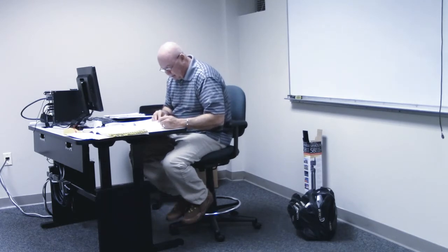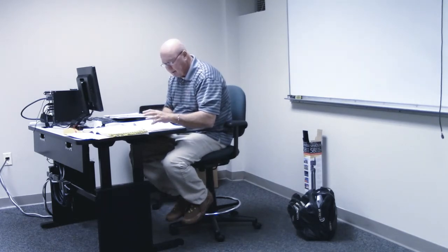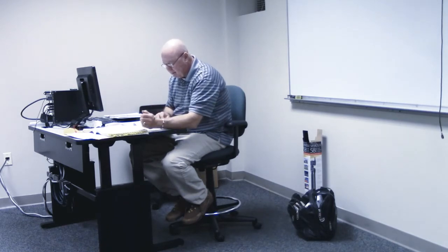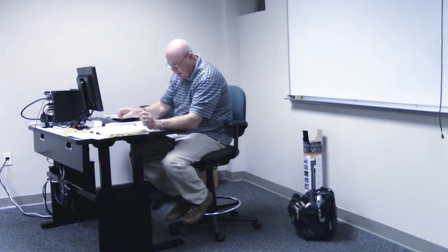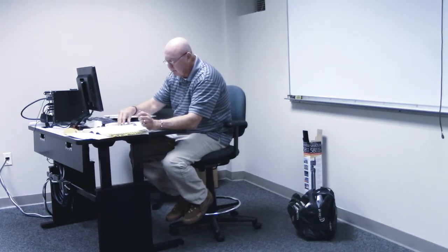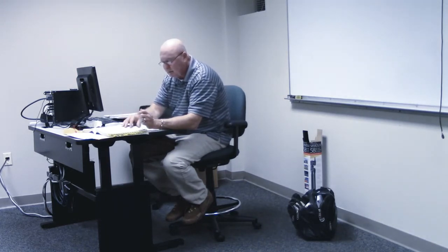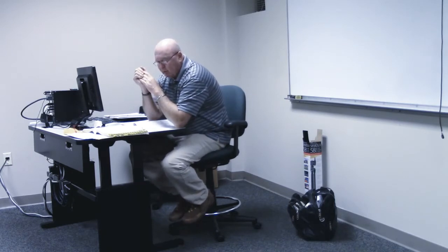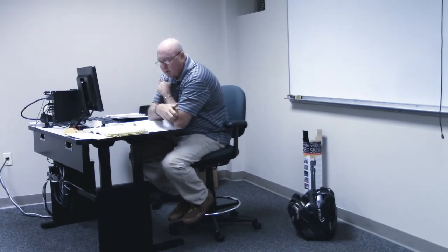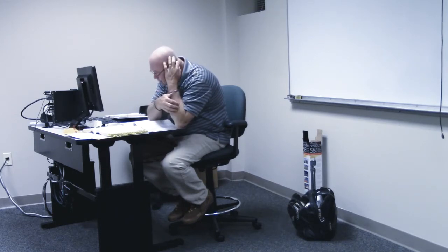Okay. So as we see these, most of these we see here in the references is 517.60 as far as wiring, and we go back to 517.60 in our code book. And 6.1, I'm sorry, we see that wiring and equipment is 517.61. And it goes into detail there. It even talks about things like operating at more than 10 volts. Conductors must comply with requirements, and we see that there under number 3.